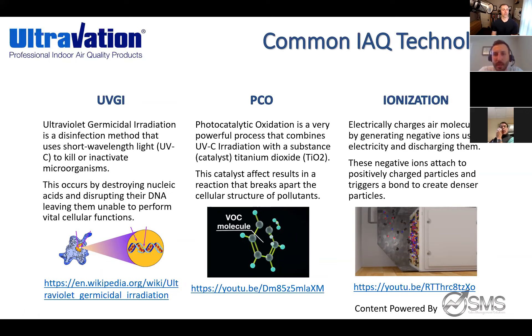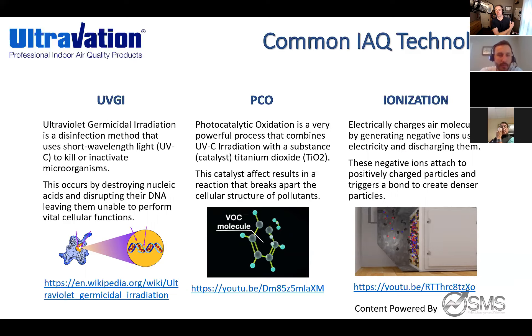Our common IAQ technologies are UVGI, PCO, and ionization. UVGI is ultraviolet germicidal irradiation — a disinfection method that uses short-wavelength light, UVC, to kill or inactivate microorganisms. This occurs by destroying nucleic acids and disrupting their DNA, leaving them unable to perform vital cellular functions. The key takeaway: UVGI is the method that uses UVC to kill or inactivate microorganisms, and you need UVC lamps to get UVGI technology.